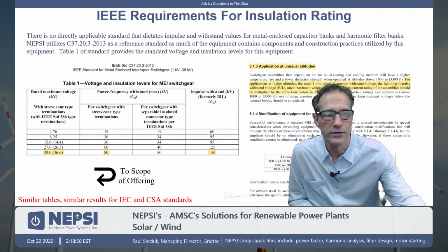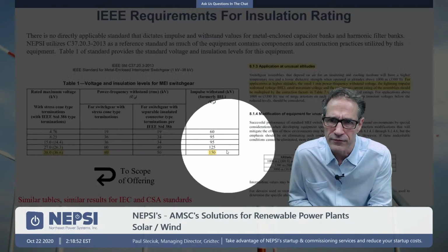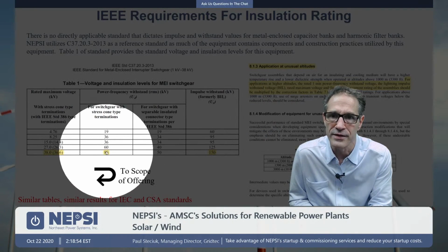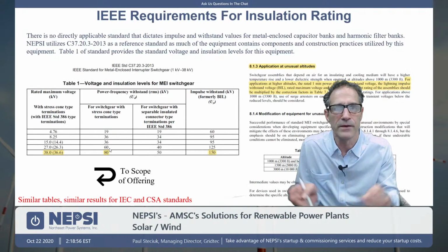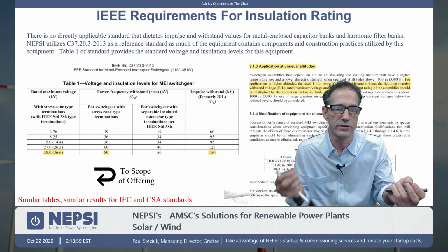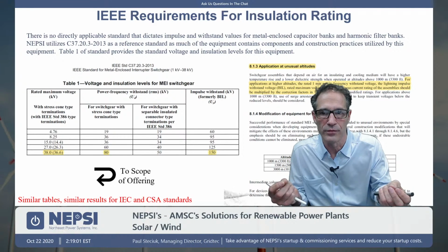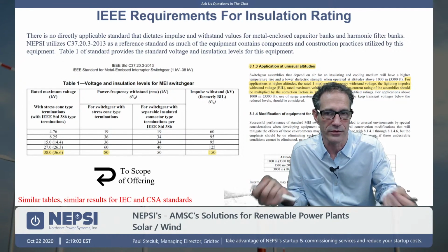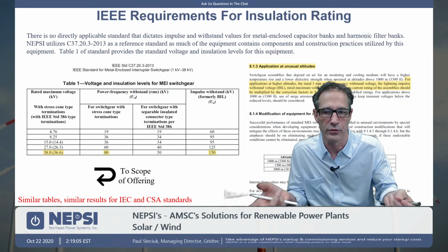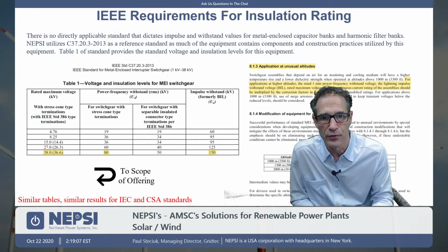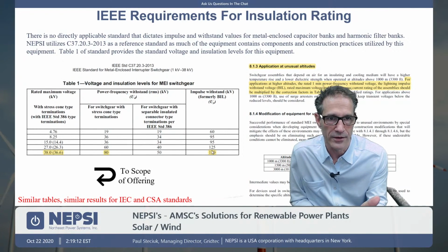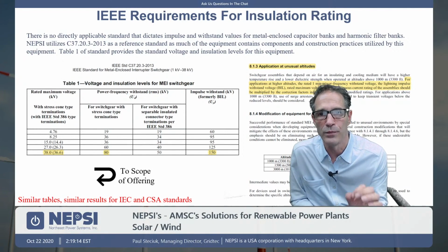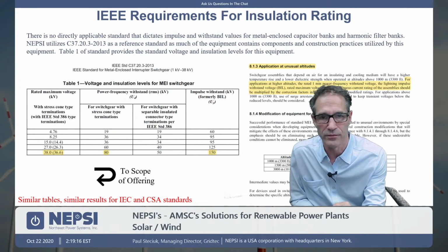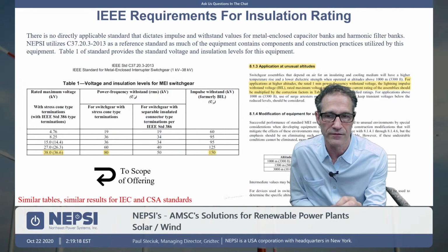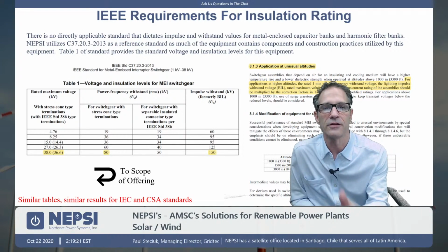C37.20.3. You will see that here, for a 38 kV gear, the requirement is 80 kV withstand, which means basically we're going to put 80 kV across the terminals of the equipment to ground, and we're going to test for 1 minute. So it's 80 kV withstand. It's a 1 minute withstand, and the impulse rating is 150. You do not need to have 200 kV BIL.